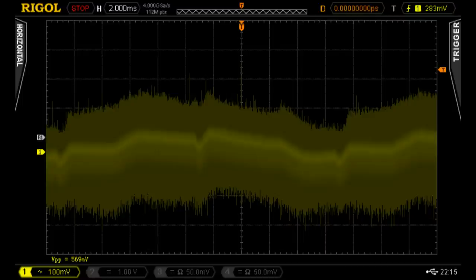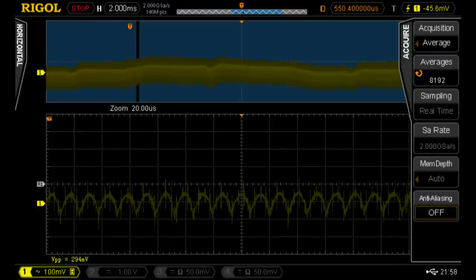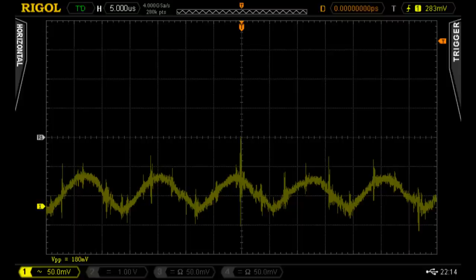If we now select a small portion of this signal shown on the top trace, we'll see that a window appears and the magnified version of what's in that window in the lower trace. This reveals a higher frequency component which has a period of roughly 14 microseconds. This works out to be about 70 kHz and it's a fairly typical switching frequency of this type of unit.